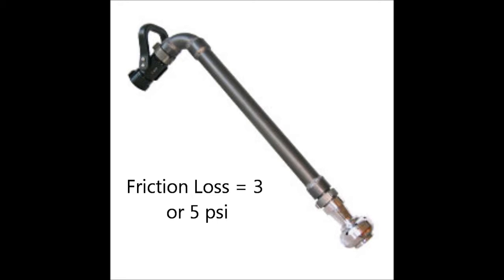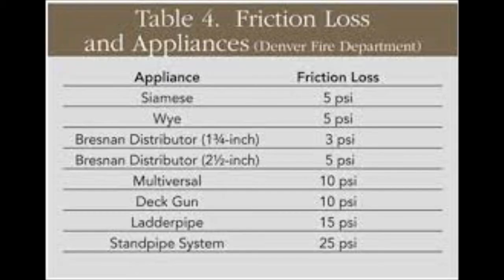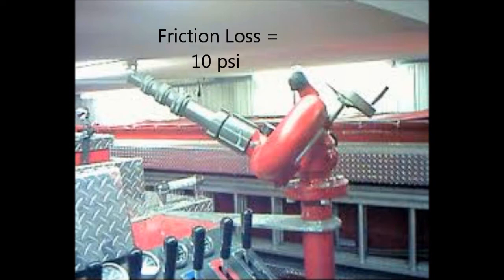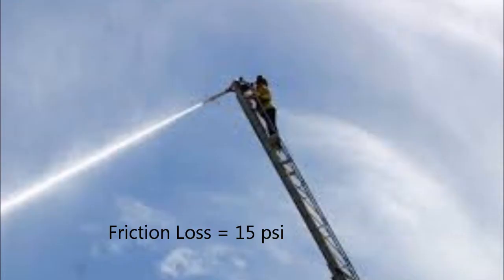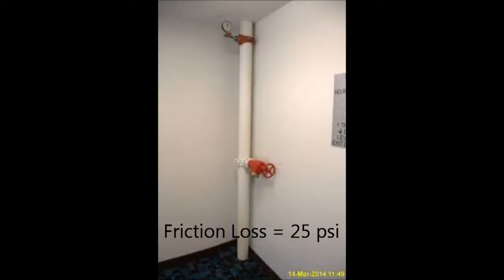The Bresnan distributor has a friction loss of 3 psi or 5 psi depending on its size. The multiversal has a friction loss of 10 psi. The deck gun has a friction loss of 10 psi. The ladder pipe has a friction loss of 15 psi. The standpipe system has a friction loss of 25 psi.